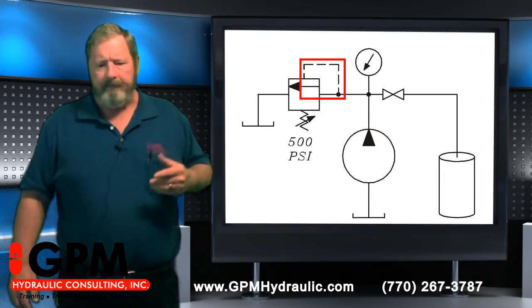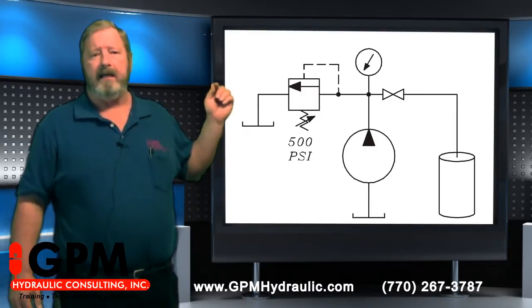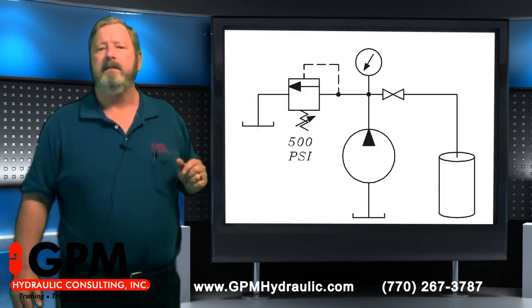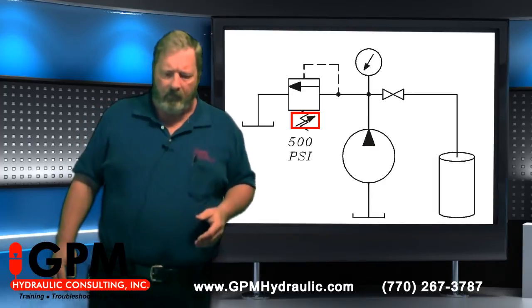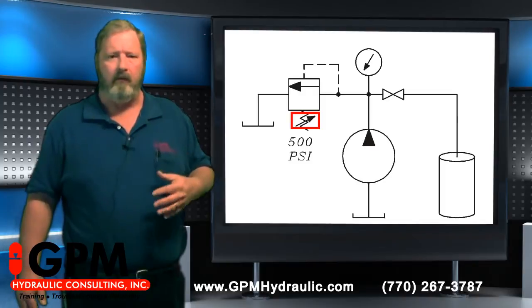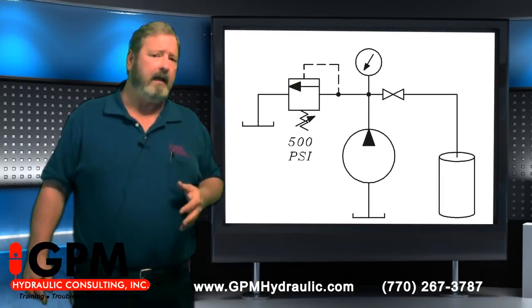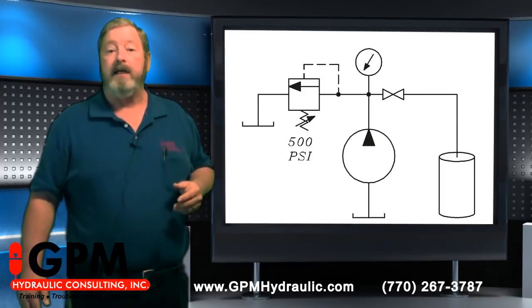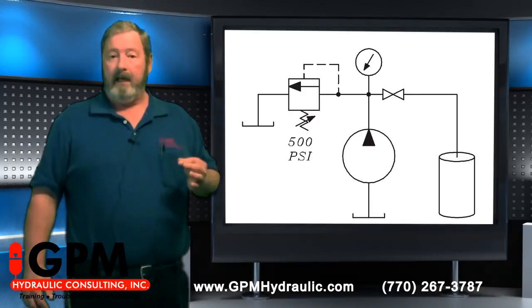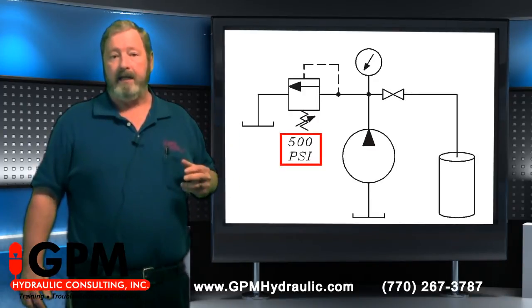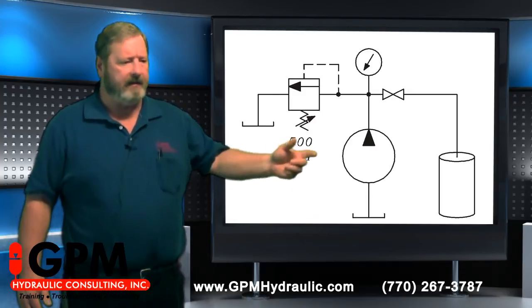You see the dotted line. The dotted line on a hydraulic schematic means a very small line, usually a pilot line or a drain line — this is a pilot line. Now, according to Pascal's law, which states that pressure in a confined body of fluid acts equally in all directions, the pressure in the pilot line will be equal to the pressure in the main hydraulic line. Notice on the spring that there's a 45-degree angle arrow going through it — a 45-degree angle arrow means that a component is variable or adjustable, more often than not meaning there is a knob on that component. Now, every plant has a knob turner, right? The knob turner's name is usually Not Me — who messed with the knob? Not Me. Well, the last time Not Me got hold of this knob, he set it at 500 PSI. So in order to go through the relief valve, pressure must build to 500 PSI — that's the resistance in this direction.